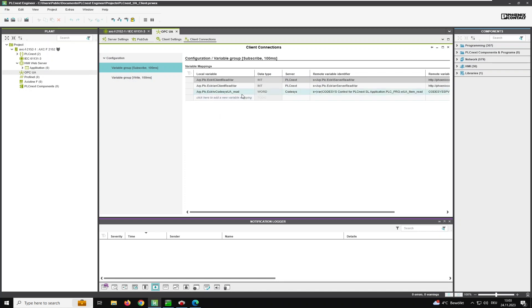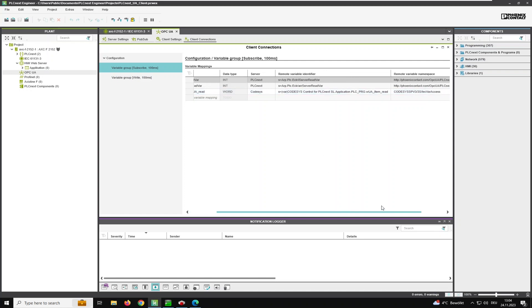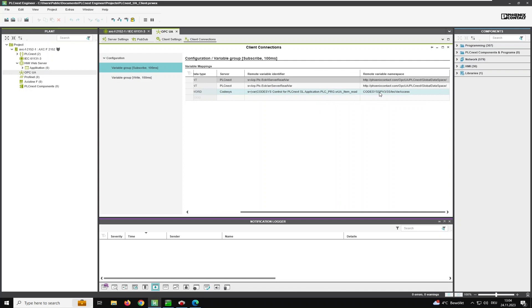Choose the local variable — this is the global variable shown before. The data type is directly detected. Choose the server which should be used — in this case, of course, Codesys. Now you can enter the remote variable identifier for this item. In addition, you have to choose the namespace. This can be done using the OPC UA expert.